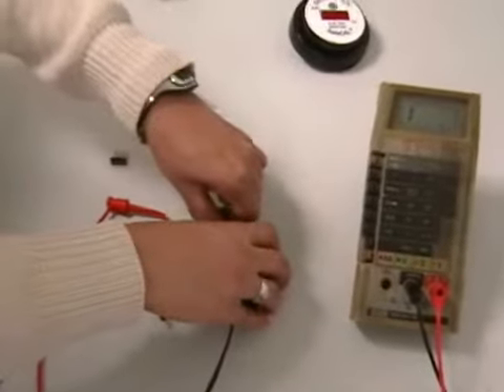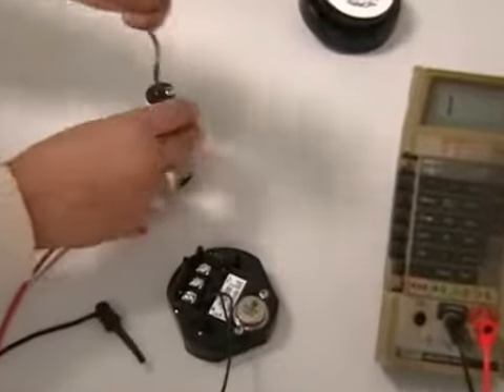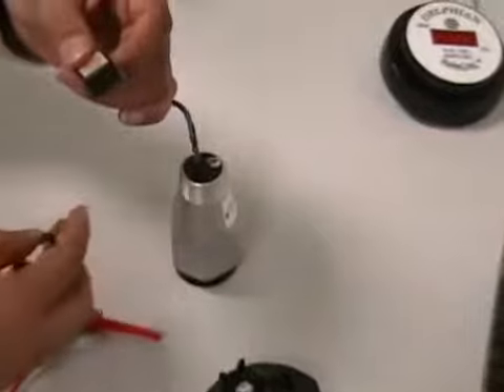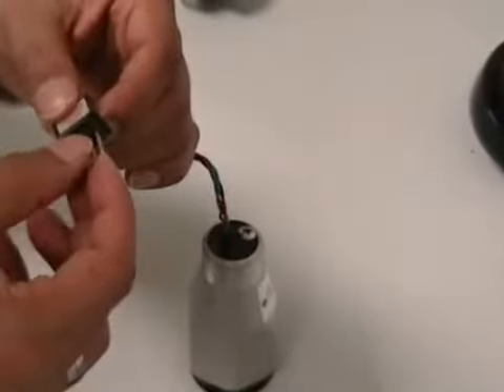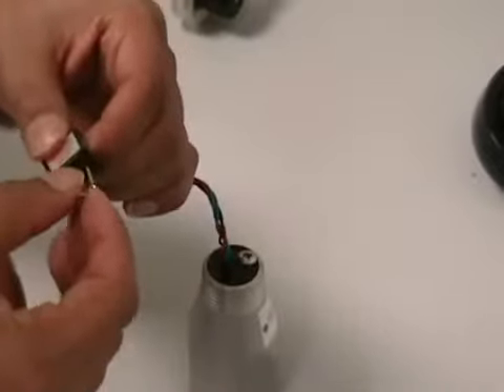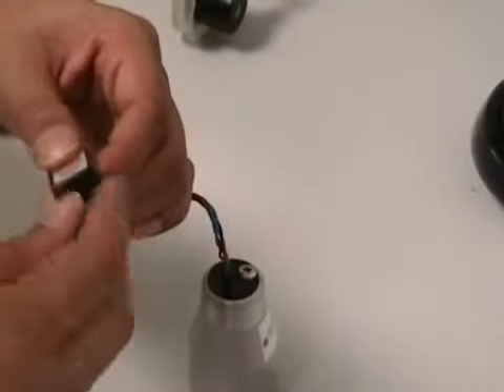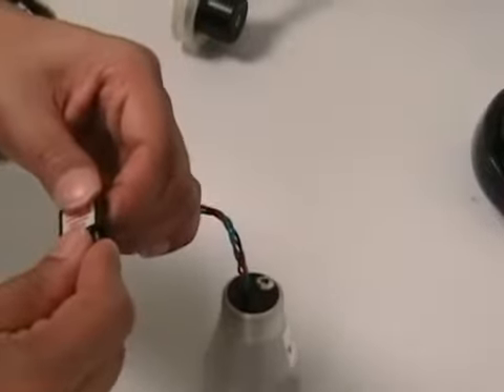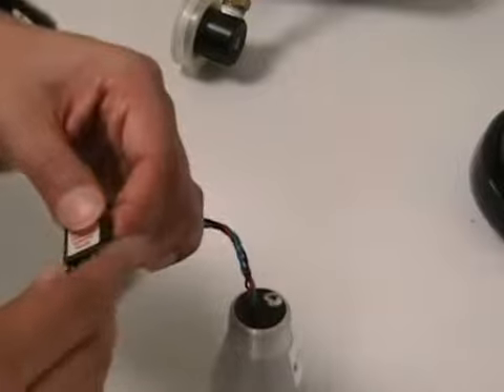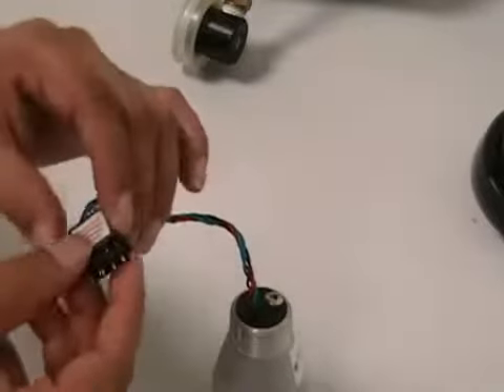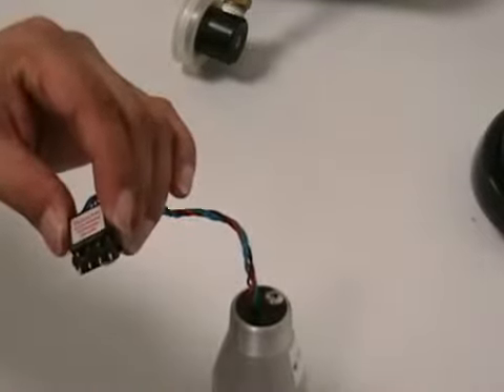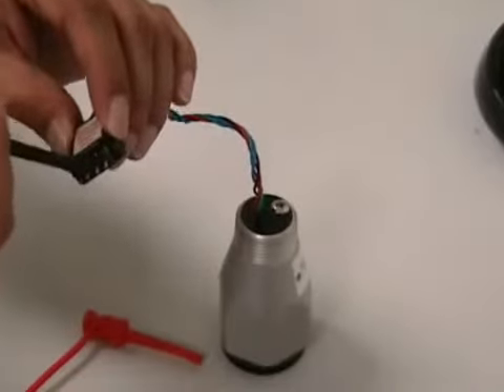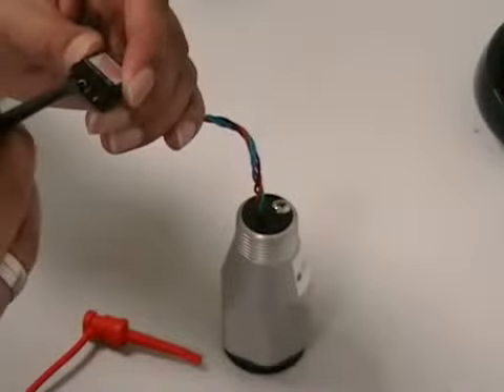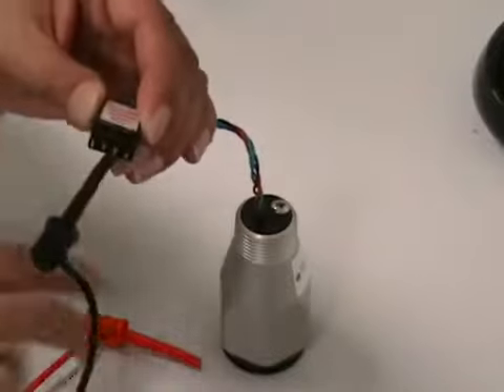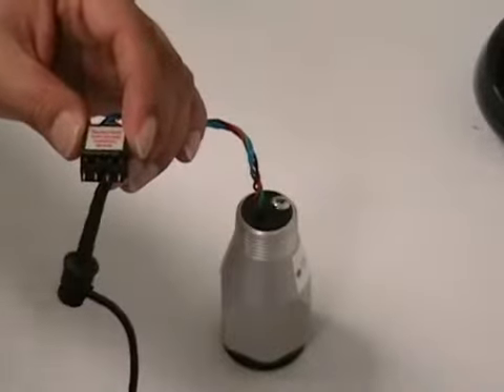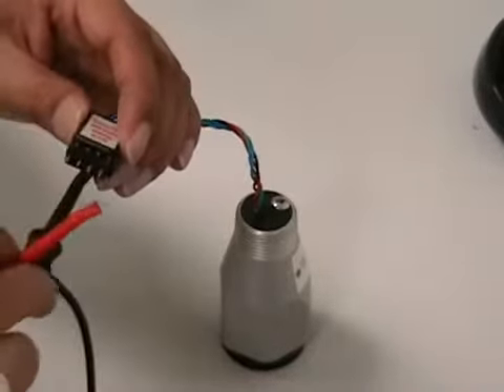Now we need to know how to test the components as separate items. With the DVM on ohm scale, test an unpowered sensor, or actually the condition of the elements, by probing between the green and red wires of the sensor for the condition of the active bead, then the green to black wires for the condition of the reference bead. These values are typically between 8 to 12 ohms. To make the probe connections easier, a 4-pin mating header can be plugged into the sensor connector.